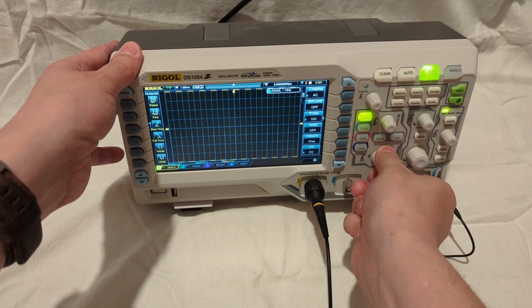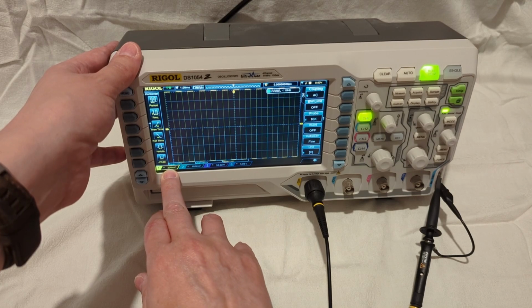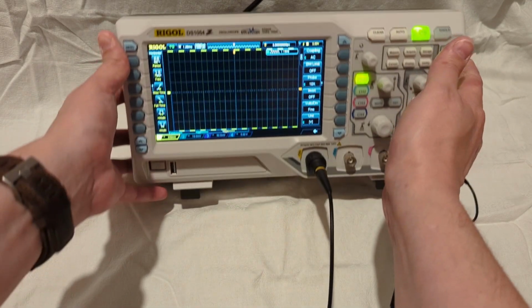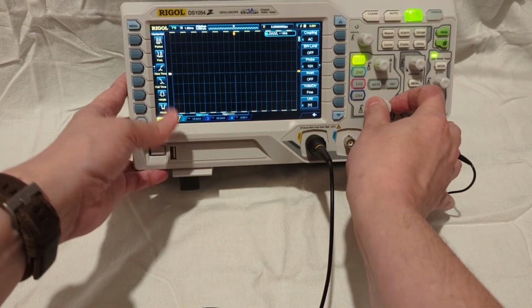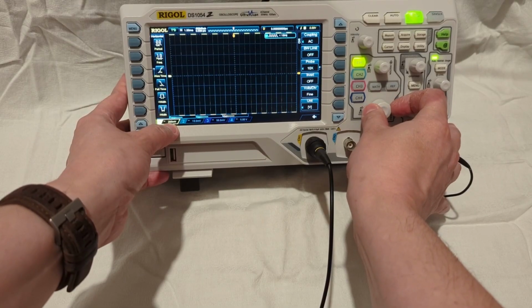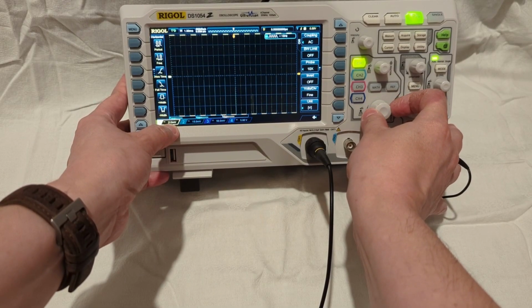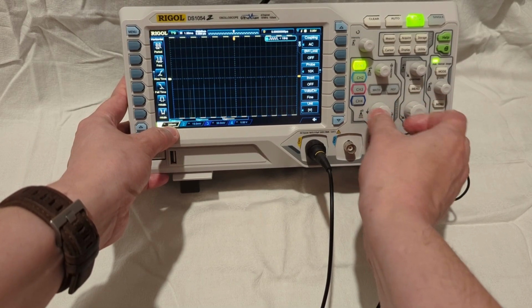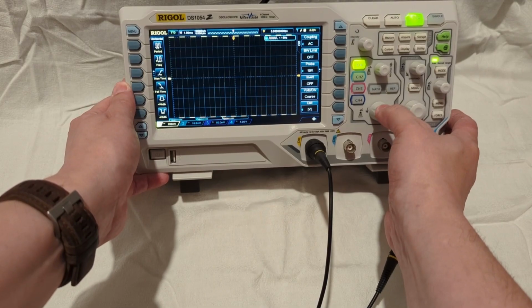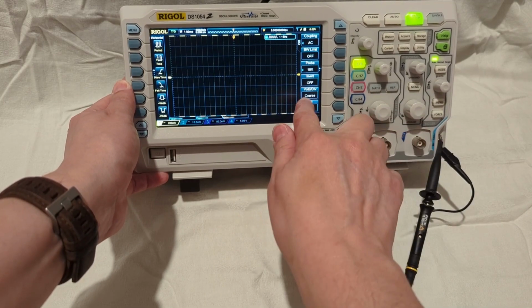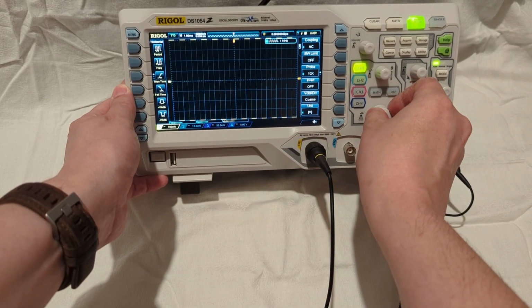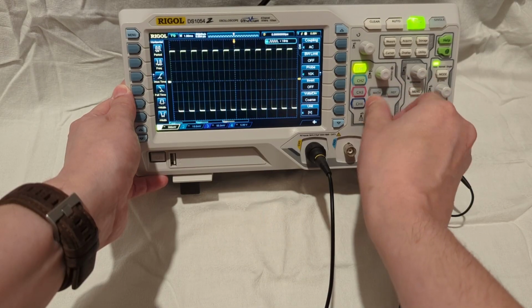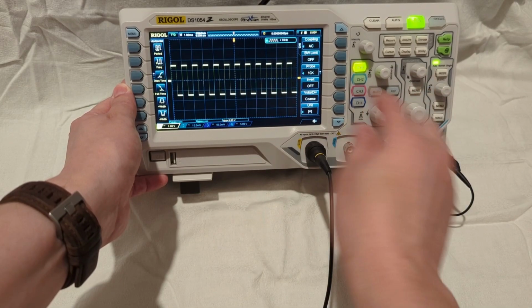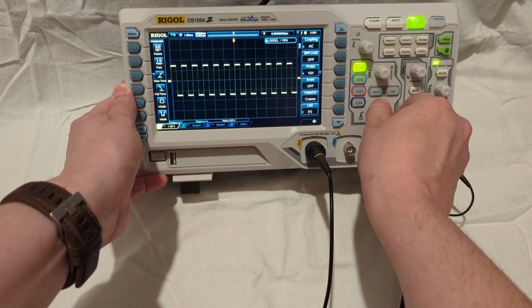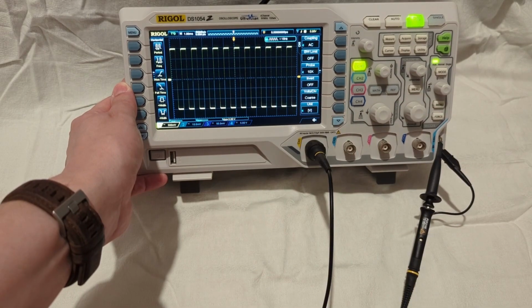Now you can see at the bottom, I'm adjusting in very small amounts. You may not be able to read it on the screen right now. Whenever I adjust this, it's going 205, 210, 215 millivolts. So if you're in that mode, you can press on this knob and it'll change from fine to coarse mode, and then we can adjust it in larger increments. So now, there we go. I've got that signal where I can see it pretty well. I'm going to go ahead and take it up one more so that it takes up most of the screen.